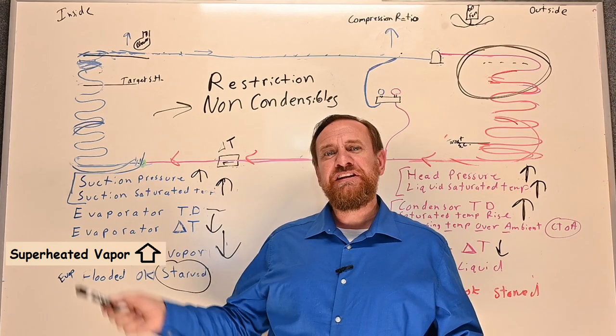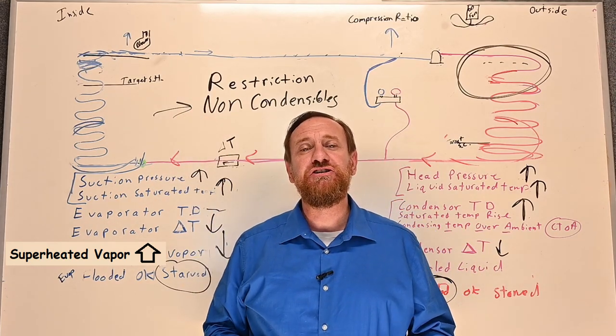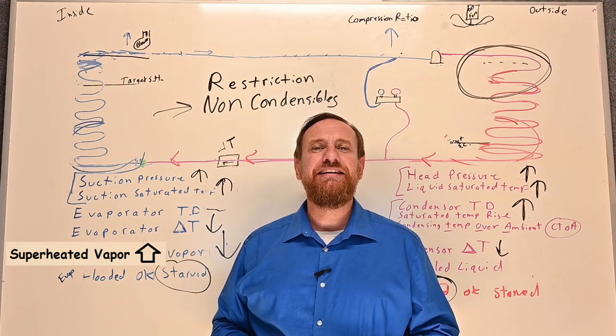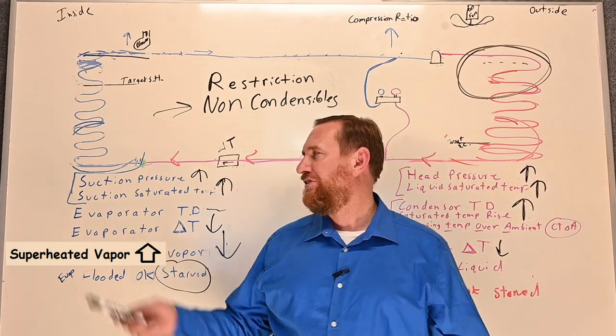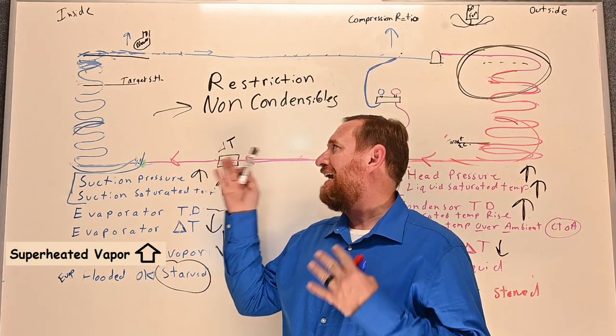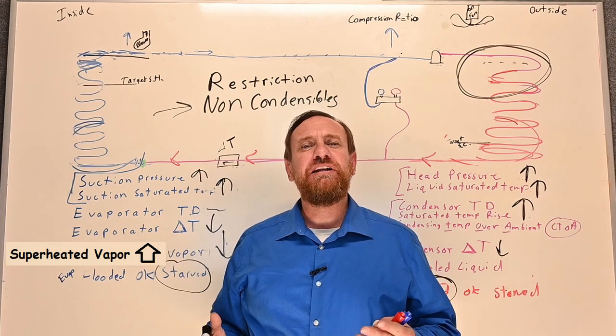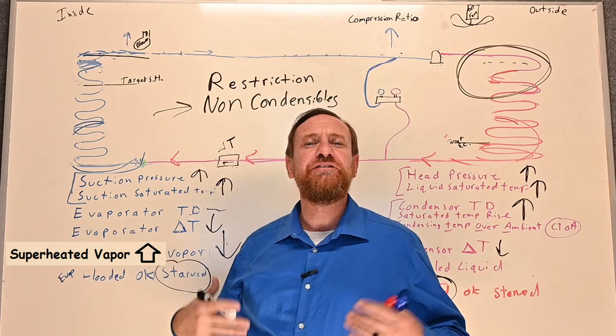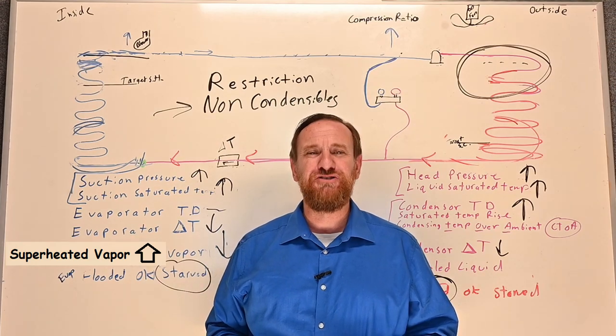After taking the system apart, checking everything, and confirming there's no restriction, put in brand new refrigerant so the system is up and running with no restriction and no non-condensibles issues. If after all that you're still getting signs of a restriction, it's most likely the TXV. In that case, simply pump the system down, store the refrigerant in the condensing unit, and change the TXV. That gives you an idea of how to check between a refrigerant restriction and non-condensibles — ultimately the repair is very similar: put in new refrigerant and save yourself headaches.